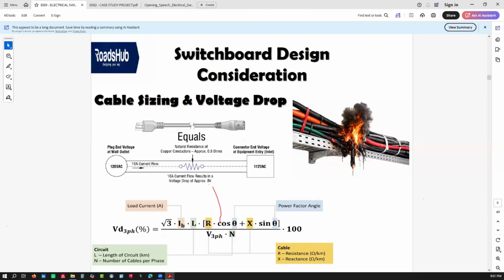If I understood this concept, I grouped it for you to know: this is the load current, this is the length of circuit and the number of cables per phase, this is the power factor angle. If you can get the purpose of the formula, you can master why I'm calculating a voltage drop percentage to compare with the standards.